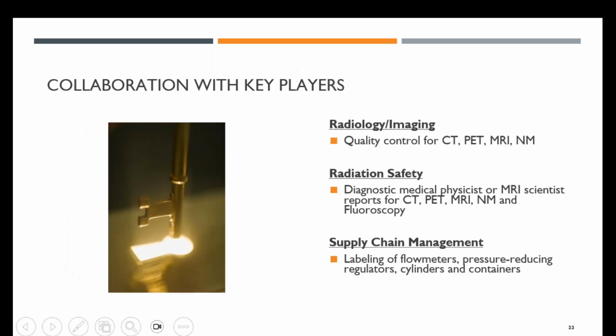So I know that's a lot, but as you can see, you need to collaborate with a lot of different departments. It's not just biomed, right? And so these are some of the key services that you need to develop your relationships with. You might need to lean on them and depend on them when Joint Commission is on site, because they may have the specific documentation that Joint Commission is going to be requesting. So radiology or imaging service, they're most likely going to have the quality control testing for CT, PET, MR, and NUCMED images. Radiation safety, they're probably going to have the physicist reports needed for CT, PET, MR, NUCMED, and fluoro.